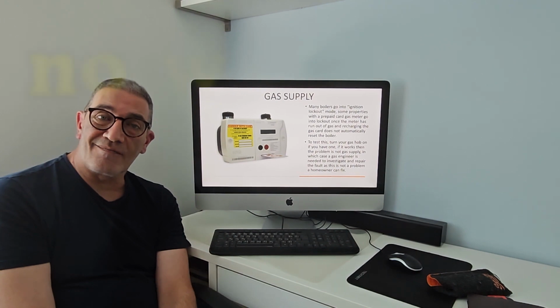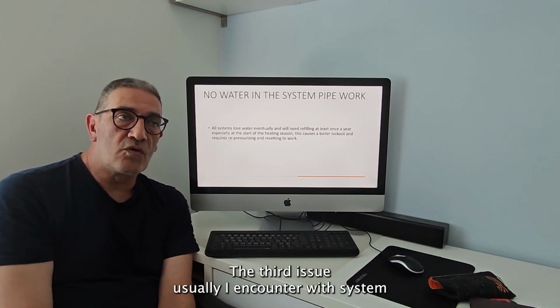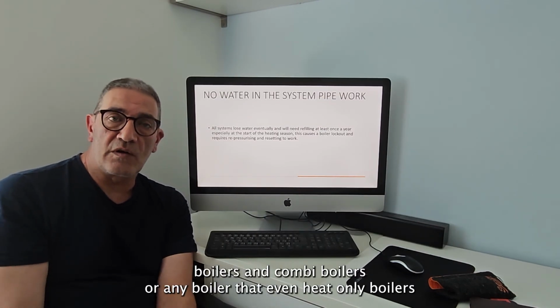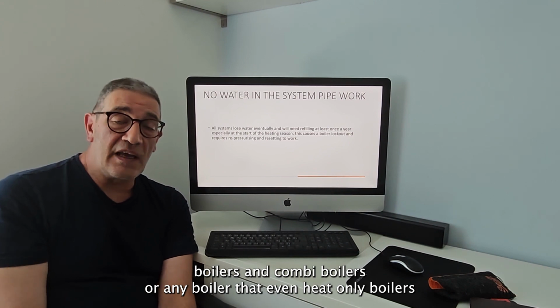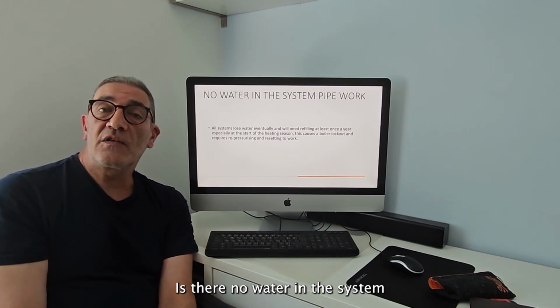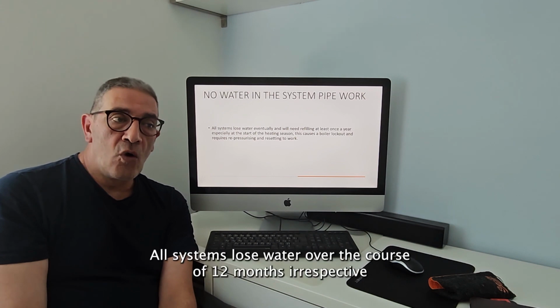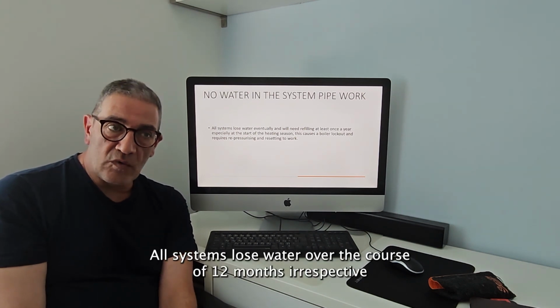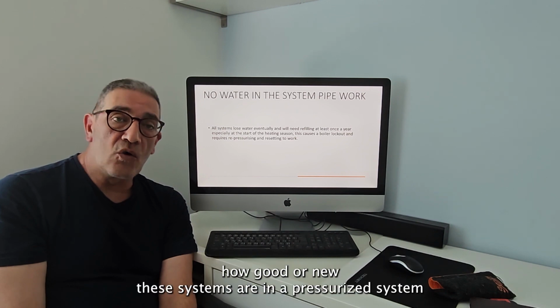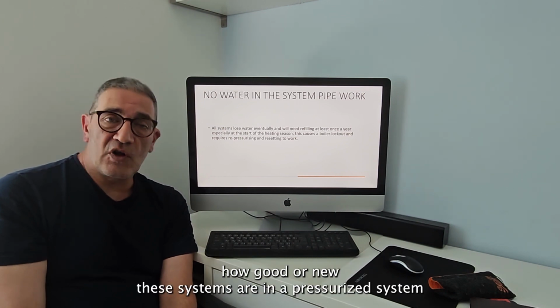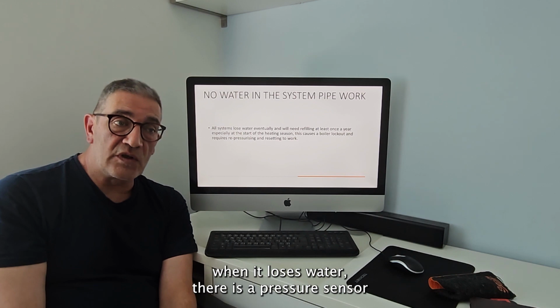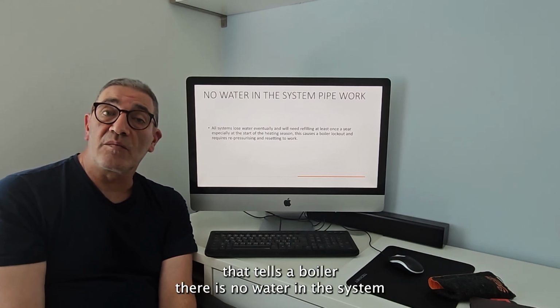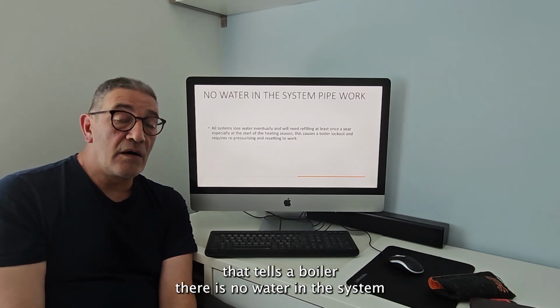The third issue I usually encounter with system boilers and combi boilers, or any boiler, and even heat-only boilers, is that there is no water in the system. All systems lose water over the course of 12 months, irrespective of how good or new these systems are. In a pressurized system, when it loses water, there is a pressure sensor that tells the boiler there is no water in the system, so it's not going to work.